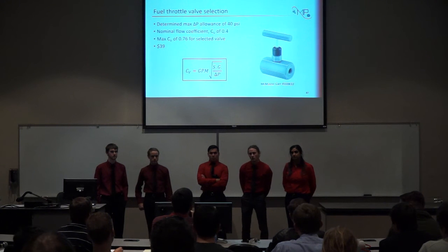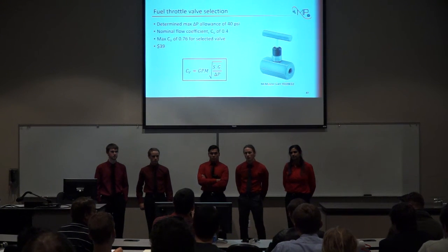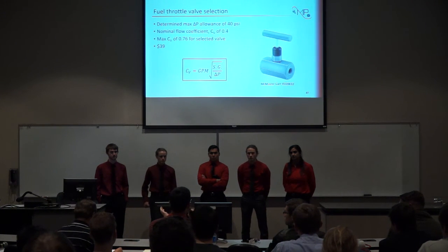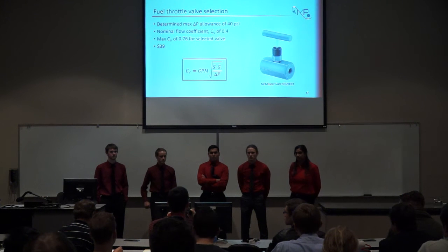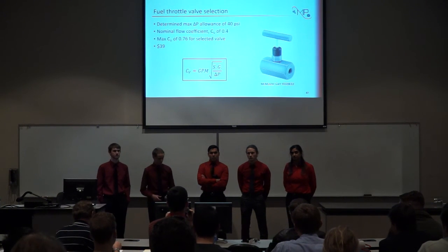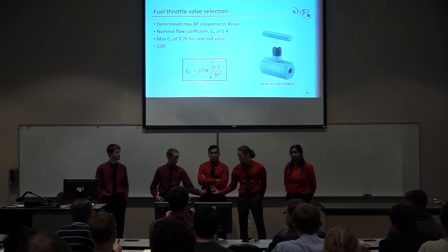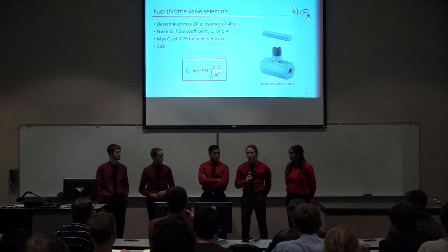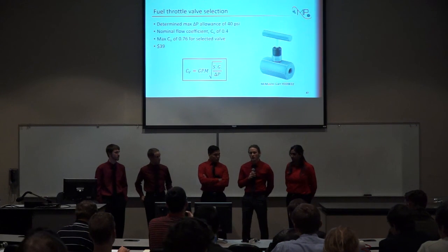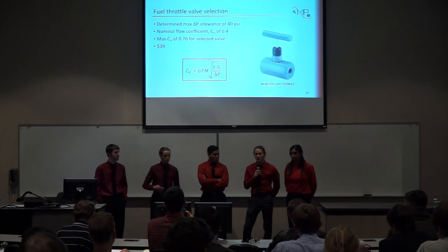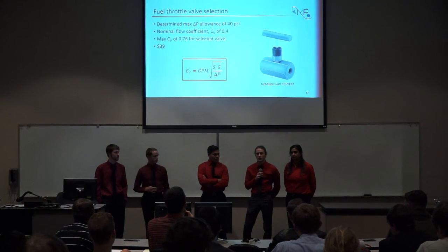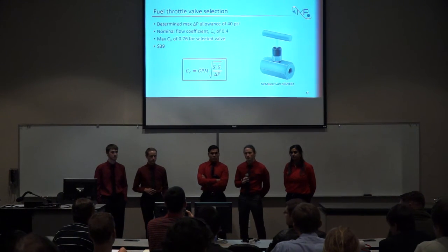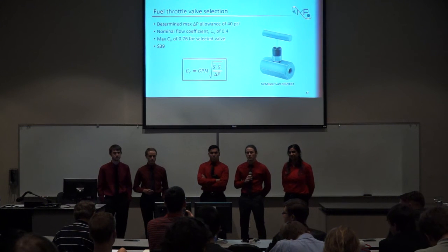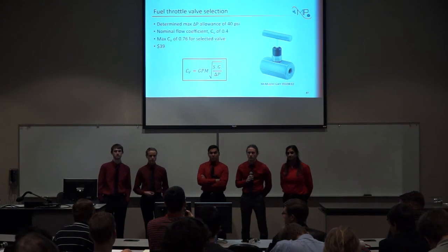Okay, it's great that you have the valve coefficient. Have you looked at what that would be for the range of flows that you would have, to make sure the operating range of that valve isn't where you're at 5% open or 95% open? Might be something to look into. Yeah, we're actually going to have to get that particular valve and do some testing with it because they don't give you plots of the CV versus turns. Okay, yeah, you just don't want to find yourself at one of those limits of the valve, open or closed.